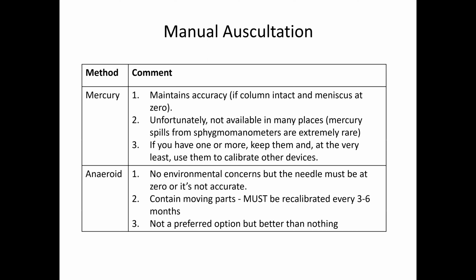And so this is why if you have a mercury lying around and haven't gotten rid of it yet, in spite of the fact that you're supposed to, don't. I mean, I'm going to give you maybe some advice not to follow regulations. Keep one around, hide one away, because you need it to calibrate your other aneroid devices. So the problem with aneroids is that they contain moving parts, and because of the moving parts, they have to be recalibrated every 3 to 6 months. And I'm going to show you that in a minute.